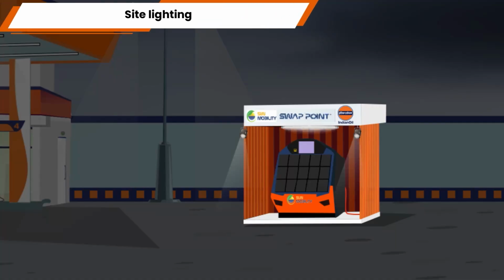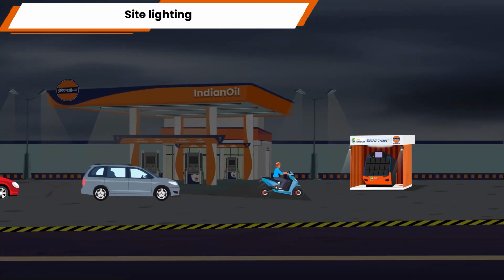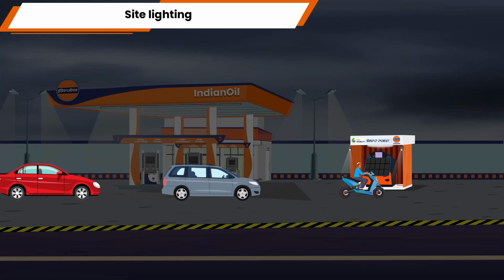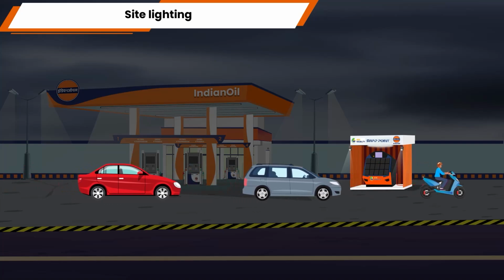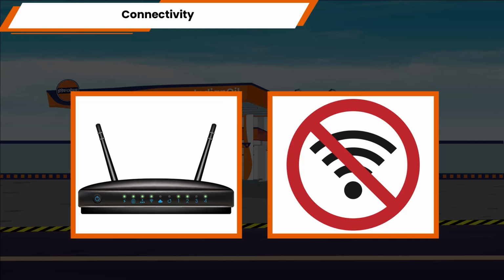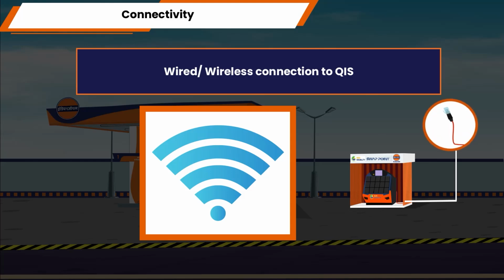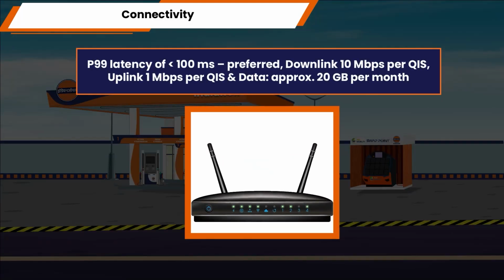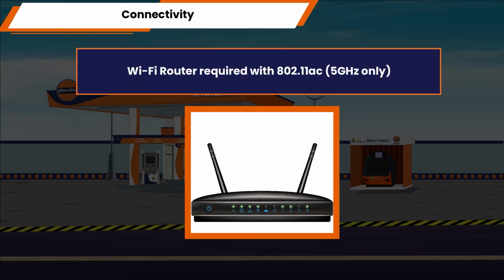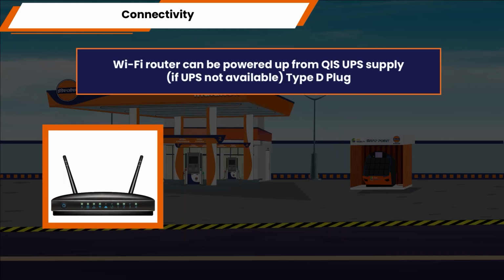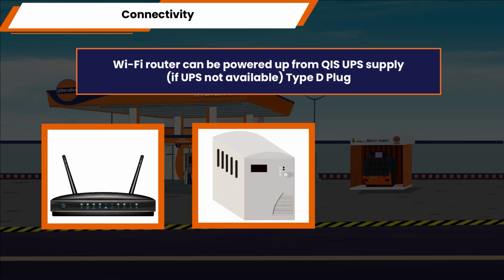Site lighting. Site lighting, approximately 350 lux, could be added if existing lights in the vicinity are not enough to ensure adequate lighting in the night and for station service when applicable. Internet connection. QIS can be integrated with an existing internet connection at site. If no internet connection exists, the following is required: wired or wireless connection to QIS, P99 latency of less than 100 ms, preferred downlink 10 Mbps per QIS, uplink 1 Mbps per QIS and data approximately 20 GB per month. Wi-Fi router required with 802.11 AC 5 GHz only. Wi-Fi router can be powered up from QIS UPS supply if UPS not available. Type D plug.